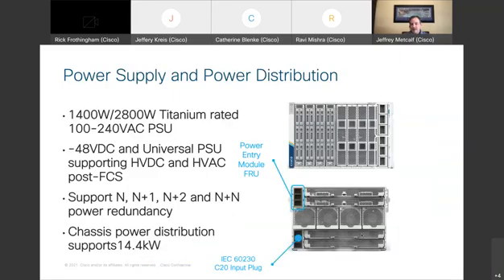Now I want to transition into power. At initial launch, we'll be releasing a titanium-rated power supply that supports high line and low line. The output capacity at high line, 200 to 240 volt AC, is 2.8 kilowatts or 2,800 watts. At low line, 100 to 120 volts, it's 1,400 watts. The reason is power is a multiple of current and voltage—if you reduce the voltage, you reduce the output of the power supply.